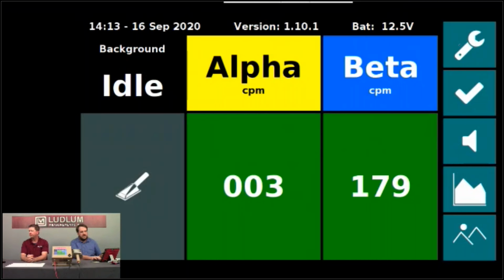On the right side of the screen, we have the settings button. These are the touch controls. The next button down is the acknowledge button. That will acknowledge the audio from an alarm. The next button down is the click audio. If you click that, it will cycle between click audio being off and on. The next button down is the background subtract, and that will subtract the current background from the live readings. You can't do it in the idle mode, so I can't show it right now, but that's that button, and it indicates the current state of it.